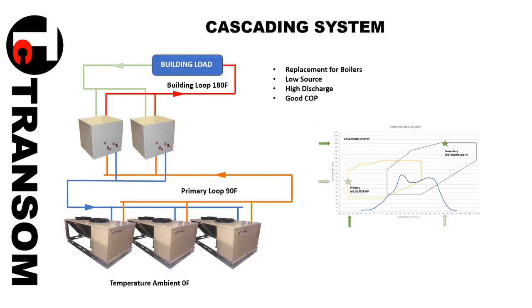Yeah, so we looked at this cascading one. We're about 2.2 to 2.4 COP at minus 30. Okay, and how about imagining not Canada, but cold winters in the mid-Atlantic? Take, say, 19 Fahrenheit. That's probably easy for you guys, but at that slightly more moderate but still cold temperature, what COP might you get at an outside air temperature of, say, 17 Fahrenheit? At the upper end you're probably up about 3.5 or so when you get up to 60 degrees out there, so it's fairly linear in between.